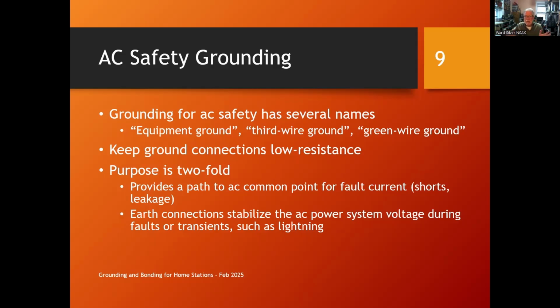All of these thousands upon thousands of ground connections, they're not necessarily all that good, but there's so many of them in parallel that they stabilize the AC power system voltage during faults or transients such as lightning or accidents or something falling on the lines. You don't want the whole system going to crazy voltages because it loses its ground reference. So you provide this ground reference, this reference potential along the surface of the earth, and that helps keep everything stable.